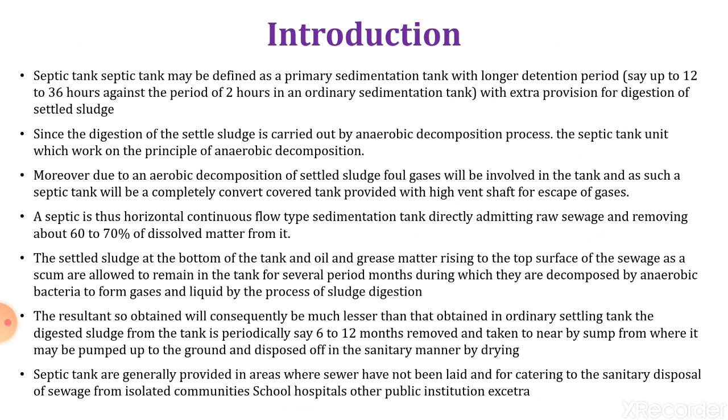Since the digestion of settled sludge is carried out by the anaerobic decomposition process, the septic tank is a unit which works on the principle of anaerobic decomposition. Moreover, due to anaerobic decomposition of settled sludge, foul gases will be evolved in the tank, and as such, a septic tank will be a completely covered tank provided with a high vent shaft to let the gases escape.